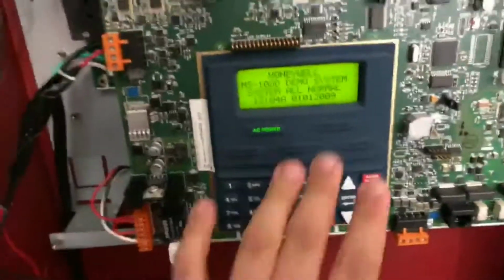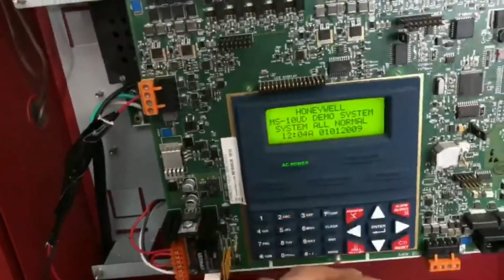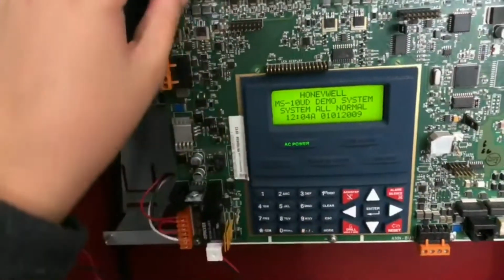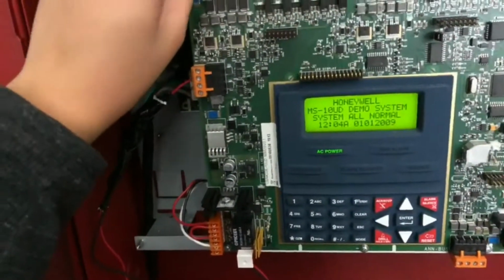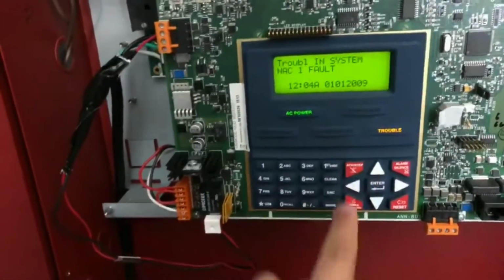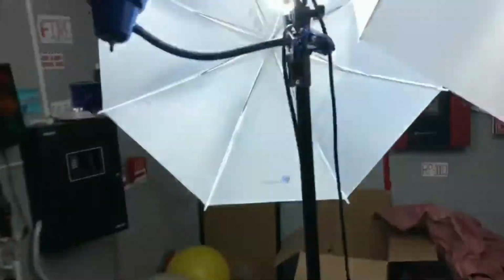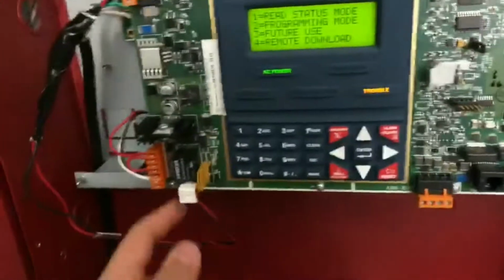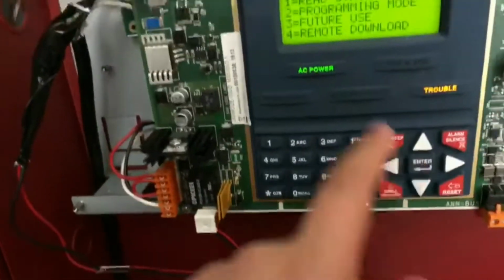And today I'm going to show you guys the difference between master programming and maintenance programming on this panel. So I'm just going to take the NAC out so we don't activate anything. So it will pop up with the trouble. I'm using the battery hack like I did over on that panel, except I'm only using the positive because this one has a charger on it.